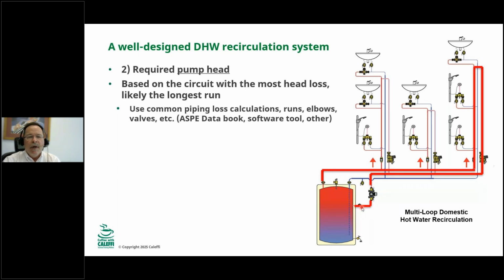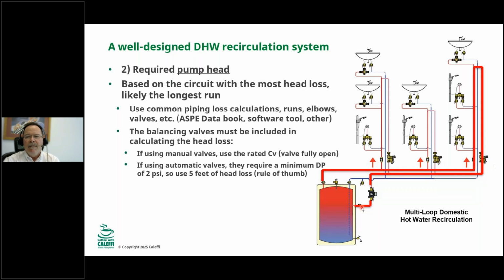So if you're using manual balancing valves, you have to use the CV of that valve, depending on which one you use. If it's a manual valve, you will find in the manufacturer's data the CV of the valve, and that's the CV you use to calculate the pressure drop across the valve at the GPM that you just determined, right? So you have to account for that.